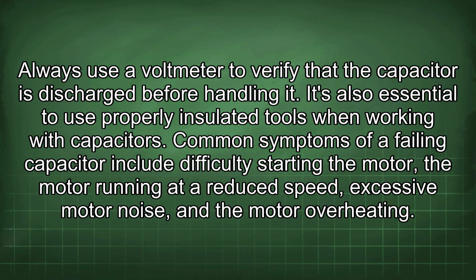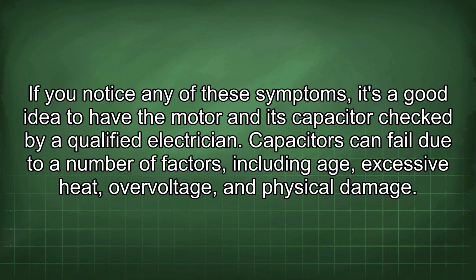Common symptoms of a failing capacitor include difficulty starting the motor, running at a reduced speed, excessive motor noise, and the motor overheating. If you notice any of these symptoms, it's a good idea to have the motor and its capacitor checked by a qualified electrician.